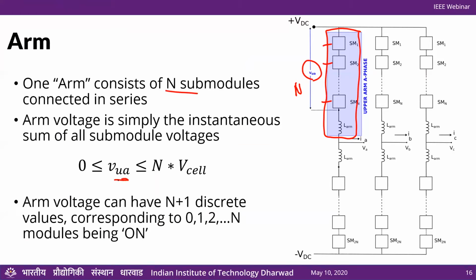To recap, there are n submodules in series. The voltage VUA is the sum of all these, so it can range only between 0, when all modules are off, up to n times V cell, where V cell is the nominal voltage of each capacitor. We cannot exceed that. Also note that VUA, measured in this direction, can only be positive, because each cell is a half bridge and can produce only 0 or positive voltage.